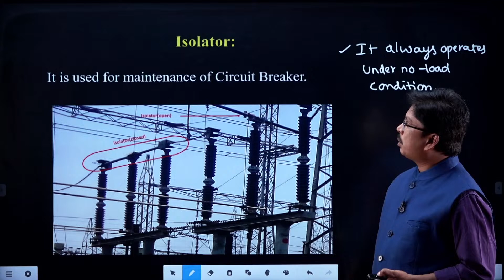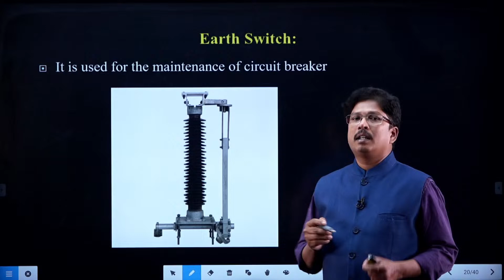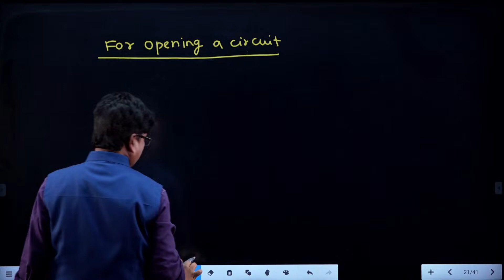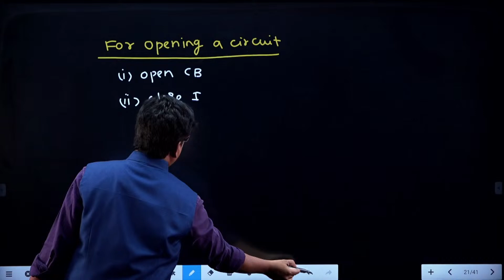Not only the isolator, one more element is there, that is the earthing switch or earth switch. It is also used for the maintenance of the circuit breaker. You can see the sequence clearly here. For opening a circuit, the sequence that you can follow is: first of all, open the circuit breaker, later open the isolator, and then close the earth switch. Clear, right? Opening a circuit means before maintenance of the circuit breaker.